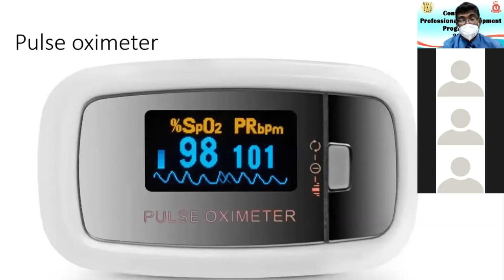Why do we say SpO2, plethysmographic oxygen saturation? Don't get confused with saturation. This is also saturation, it is all right, but here the P in SpO2 stands for plethysmograph. It measures the pulsatile waveform in the finger and gives this reading. So without a pulsatile waveform, you don't get this reading. Therefore, this pulsatile waveform is very important to interpret the correct values of the pulse oximeter reading.